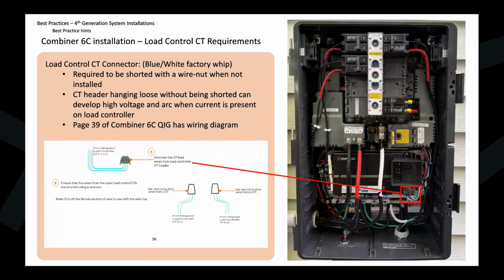So for grid-tied scenarios, we need to use the port where the factory blue and white wires are the CTs for the load controller. We need to disconnect those. That's where the wiring of the new consumption CTs is going to go. But installers are just removing that factory whip and letting it dangle in there. The harm is that it can carry current and potentially cause an arc and hurt someone. So in this picture, where my cursor is, we want to remove that header.